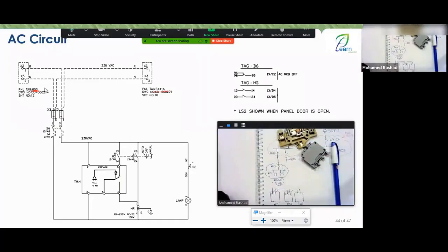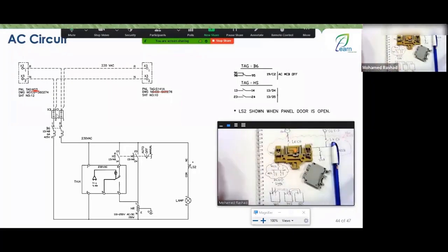Nice. Very nice. So here you have, engineer, a slide link TP. So why, engineer Rashad, a slide link TP? Because here I can isolate the AC circuit without affecting anything. For example, if I want to do maintenance here, or if I'm changing the heater or the lamp that I'm working on here, I can isolate the TP. There might be any problem, you know. The idea is that I want to isolate the supply. So you can open it through the slide link TP and thus isolate the supply. The part before the supply and the part after, meaning you completely isolate here from the section below here.